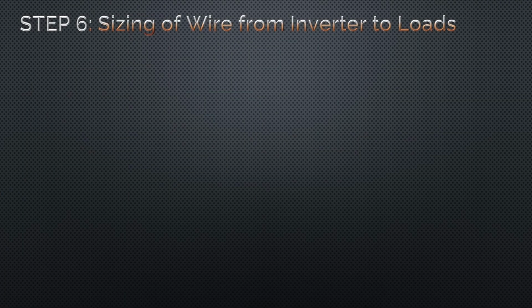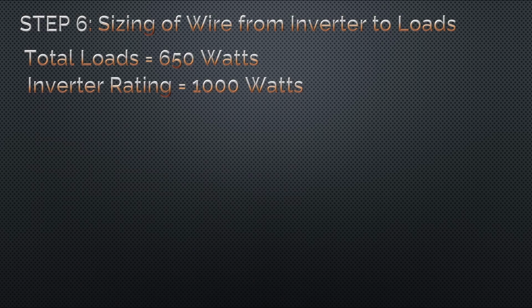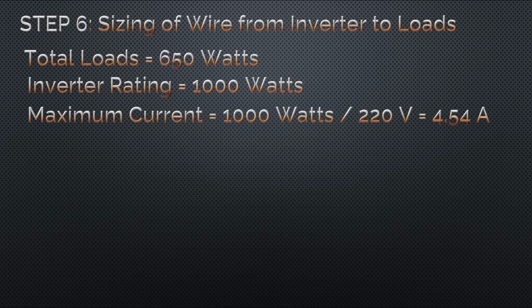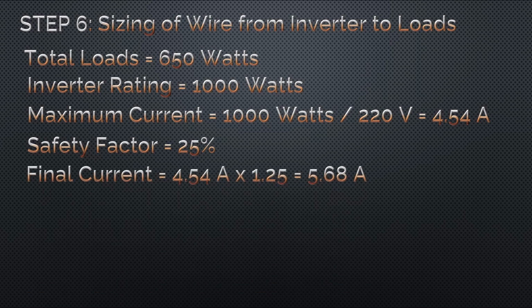To size the feeder wire from inverter to loads, you have to consider the total wattage of the loads, but sometimes you must consider future expansion. So you will use the inverter capacity. So the maximum current using the inverter capacity is 4.54 amperes. Also, you must consider applying the safety factor for continuous loads. So the final current will be 5.68 amperes. If we look in the ampacity table, we will use number 14 AWG THHN. So the AC breaker to be used is rated at 15 ampere or 20 ampere miniature circuit breaker.